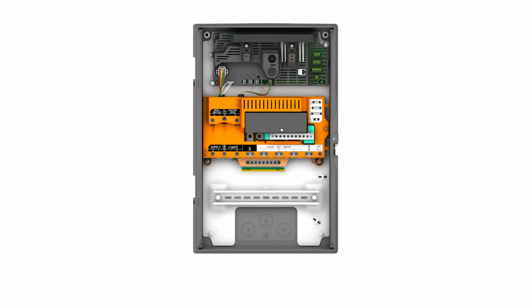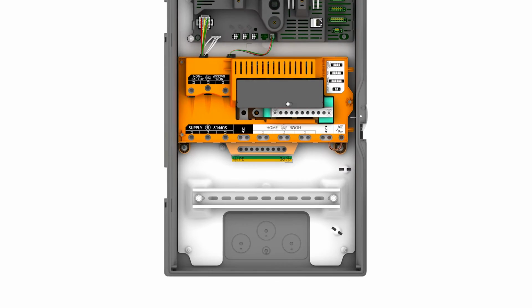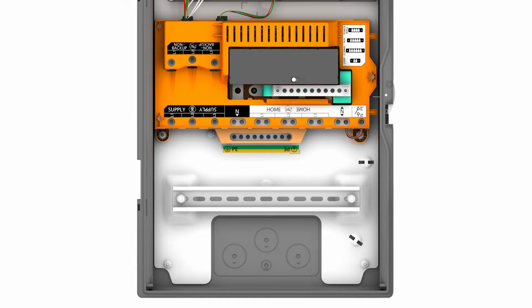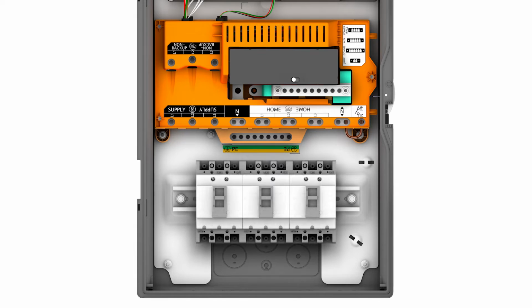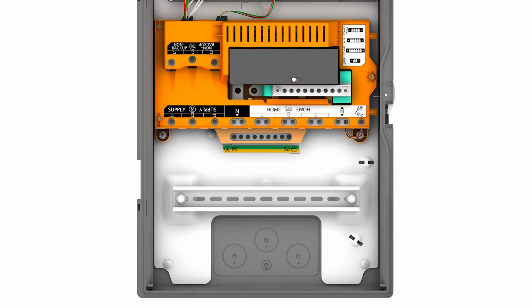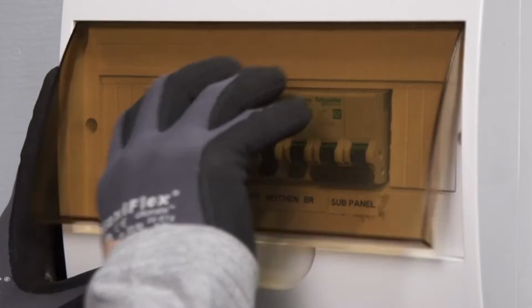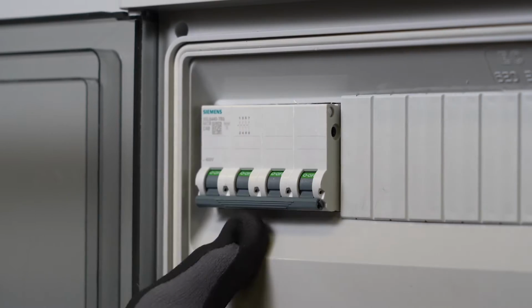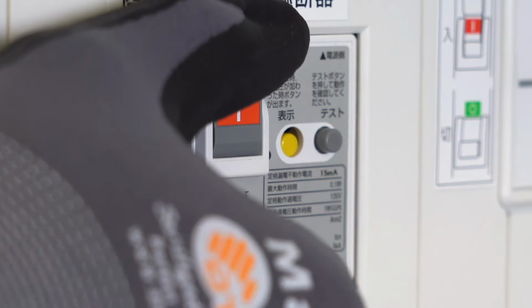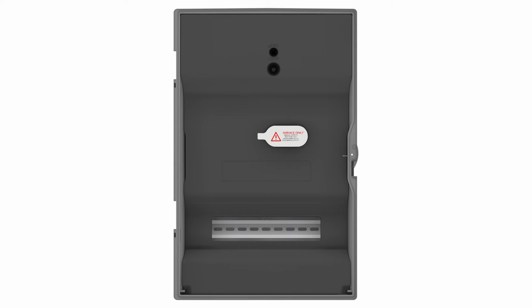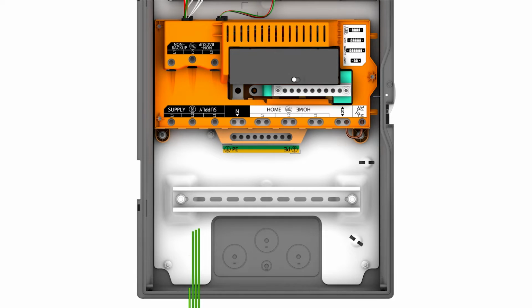With the enclosure and assembly mounted, the next step is to wire Backup Gateway 2. Installers will need to provide the circuit breakers appropriate for the job following local requirements. Before beginning any wiring, ensure that all power sources are de-energized and safe to work on. Refer to the chart on the back of the dead front cover for diagrams, torque specs, and allowable wire gauges. Throughout the wiring process, grounding conductors will be terminated on the ground bar.